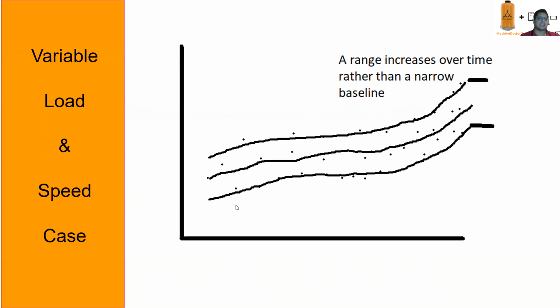All this while taking RMS of the waveform every 5 or 10 minutes, so that anomaly can be detected every few minutes, just like we did in the constant load and constant speed machine. This will still ensure that this approach is good, not just for constant load and speed machines, but also for variable speed and load operations, while reducing the power requirements, data costs, and cloud costs drastically.